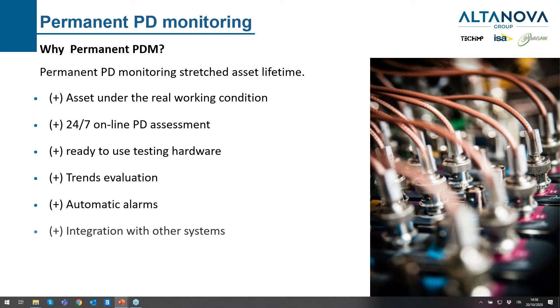We have automatic alarms, and we can integrate the partial discharge monitoring with other systems — for instance, infrared sensors and movement sensors on the cable. There are many things that can be integrated. It is, however, a bigger investment for the customer, and we have to underline the positive aspects that permanent monitoring gives and make clear the importance of such investment for the future.